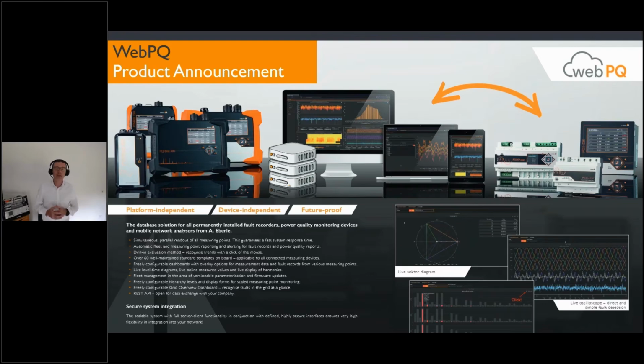So we call the software WebPQ with this cloud aspect, but it must not run in the cloud. It can also run in your system, believe me, just as a Windows service, not an issue. It is a centralized system which continuously holds the connection to the devices, maybe in the low voltage grid, maybe in the high voltage grid, and combines all the grids together in one database to find issues, to find things which are coming into the grid.